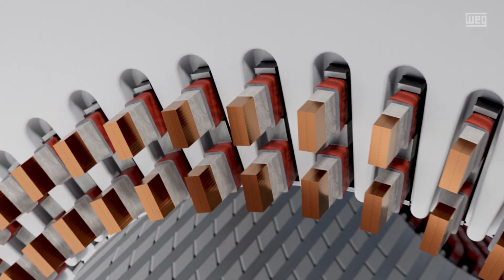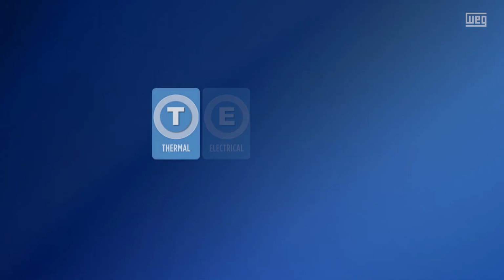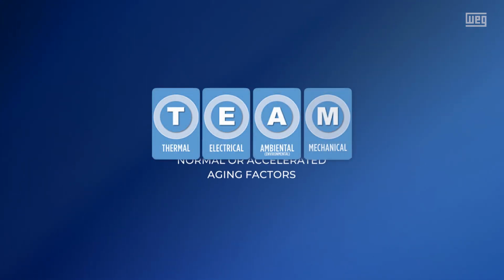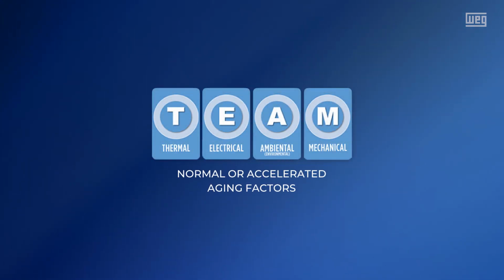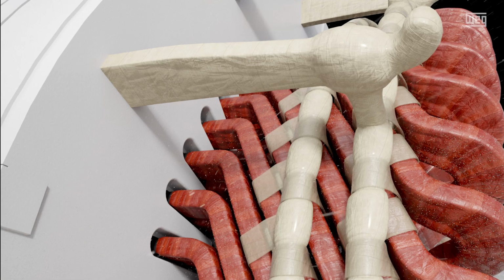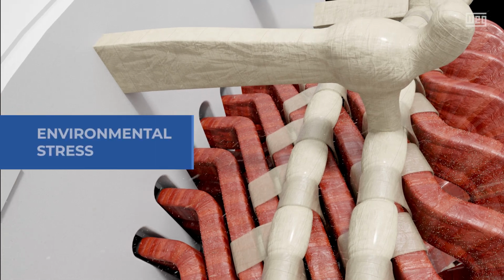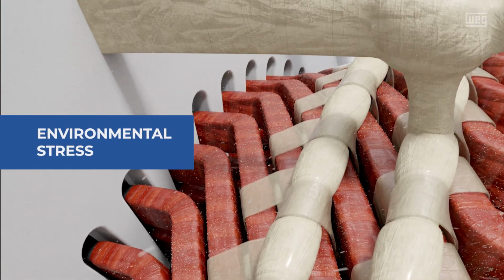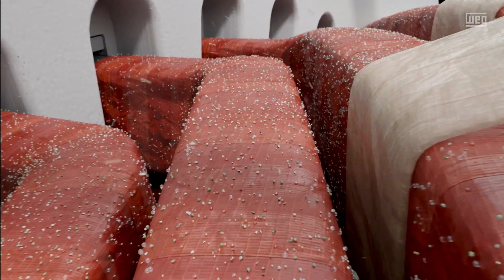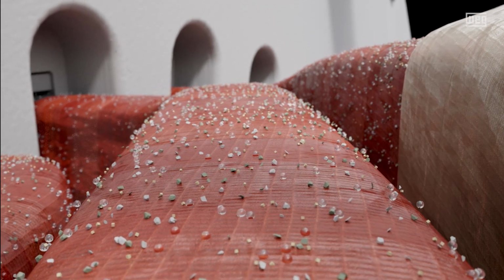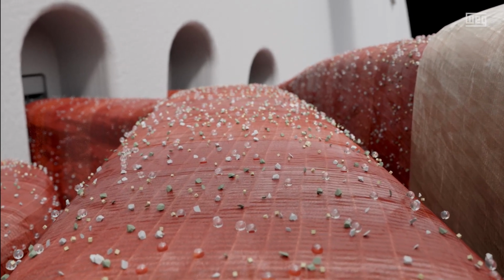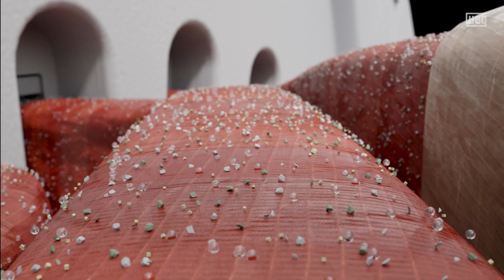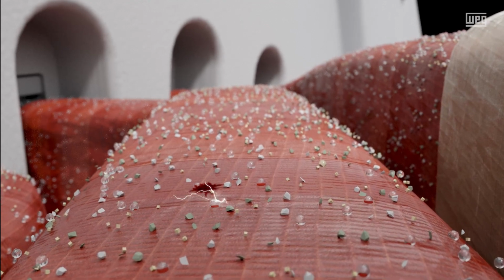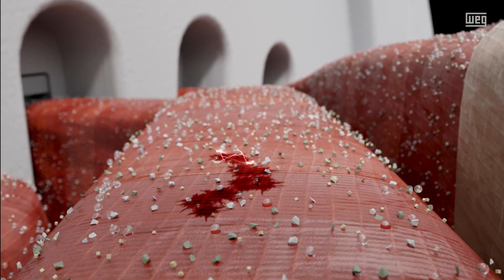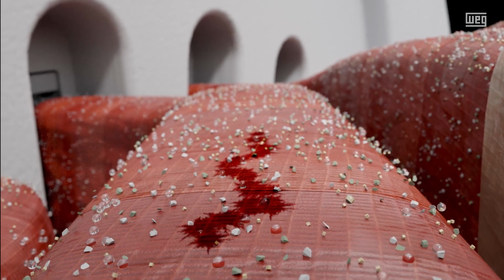Several aging factors can affect the performance of the insulation system. They have to be kept under control in order to prevent the development of accelerated aging mechanisms and significant degradation of the insulation as a consequence. The environmental stress is related to the location where the machine is installed. The accumulation of salt or contaminants combined with water can cause electrical discharges, which can develop a conductive path on the surface of the insulation.